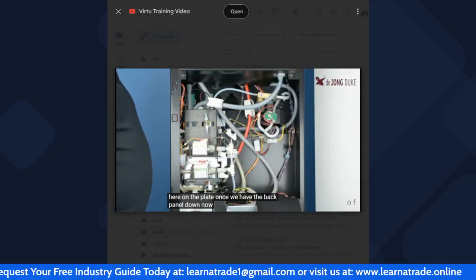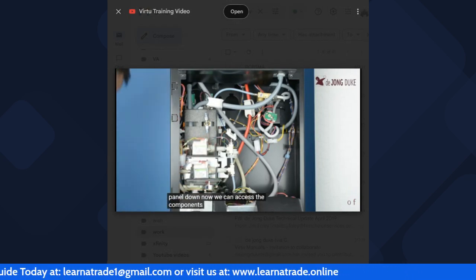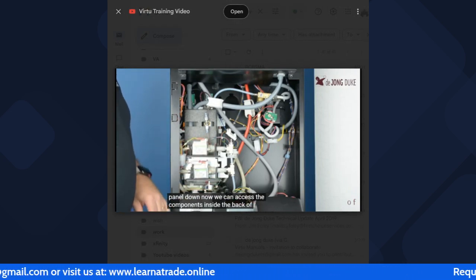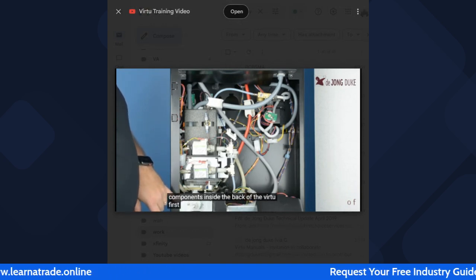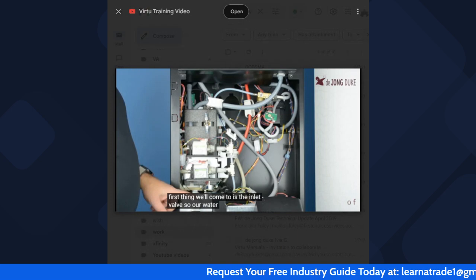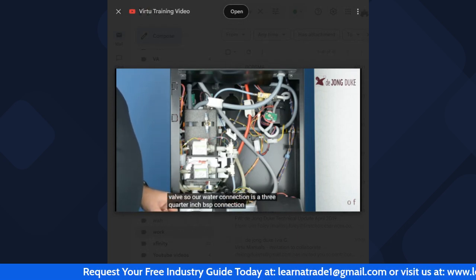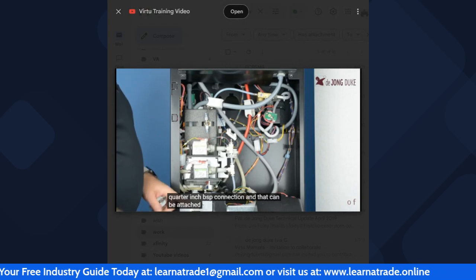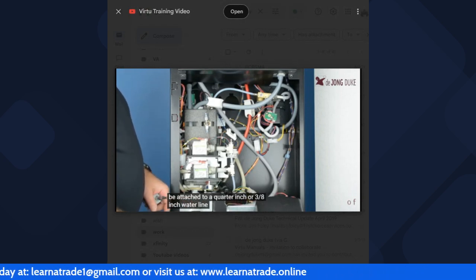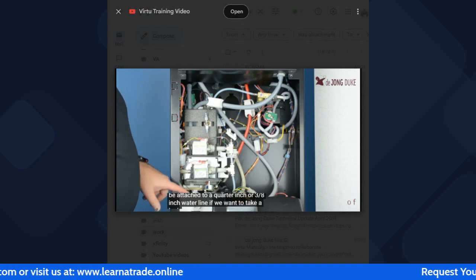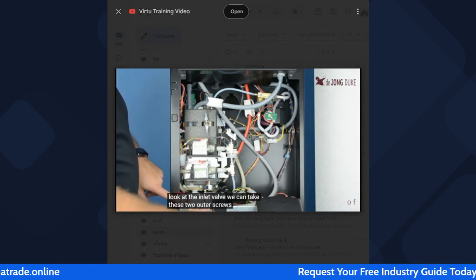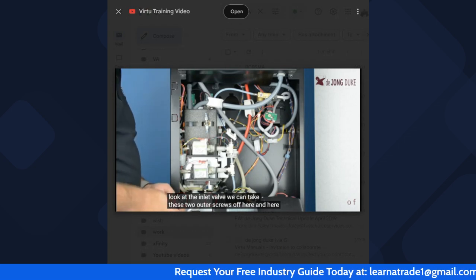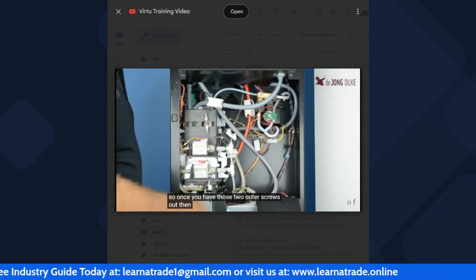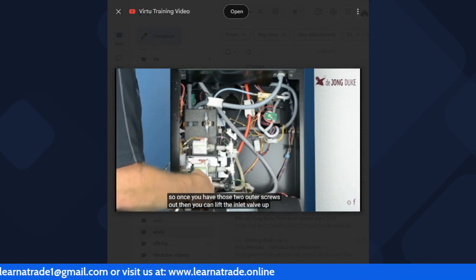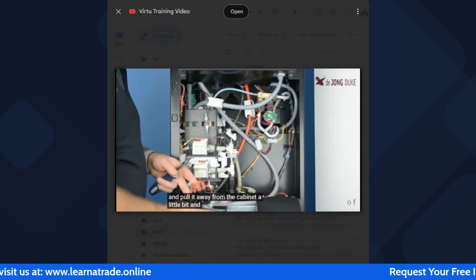Once we have the back panel down, now we can access the components inside the back of the Virtu. First thing we'll come to is the inlet valve. So our water connection is a 1/4 inch BSP connection, and that can be attached to a 1/4 inch or 3/8 inch water line. If we want to take a look at the inlet valve, we can take these two outer screws off here and here. So once you have those two outer screws out, then you can lift the inlet valve up and pull it away from the cabinet a little bit, and then we can see what it looks like.